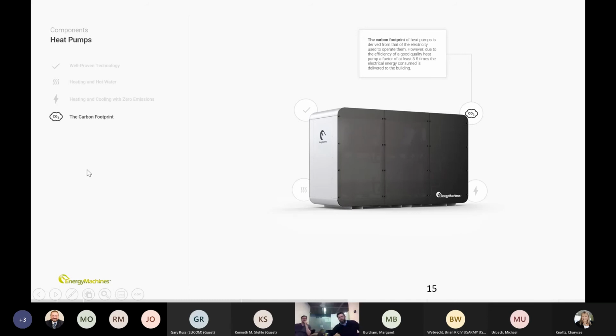We're achieving COP values - coefficients of performance - of 5 for heating; if you combine heating, cooling, and domestic hot water, you're seeing COP values of around 10. Now, I think some engineers would argue that the cooling is a byproduct of the heating, a waste product, and so depending on which side of the fence you sit on, it's a COP value of 5 or a COP value of 10.